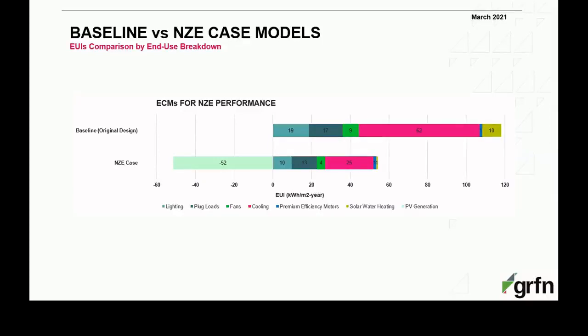So why did the load reduce? One is better envelope. Second, reduced lighting load. Third, reduced motor load. And then we have used a much more efficient system, which is using magnetic bearing chillers with an all variable plant, so VFDs on all pumps, and a water cooled system with an optimum control system. This is what led to that drastic reduction in the cooling consumption.